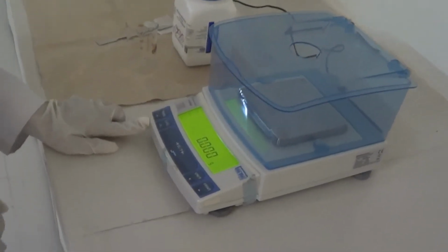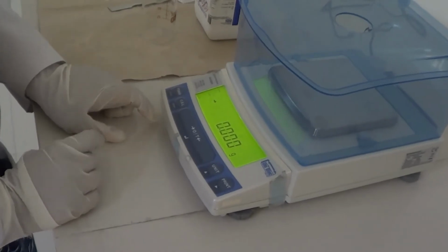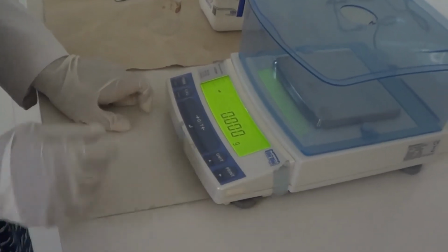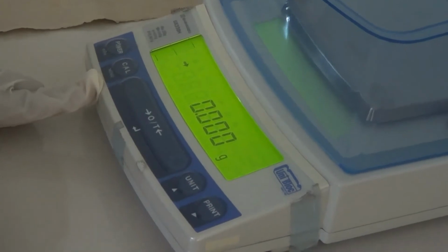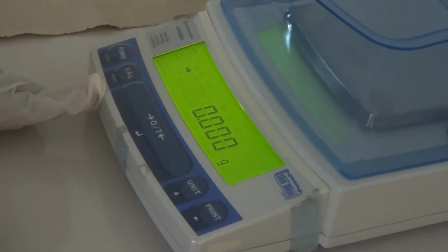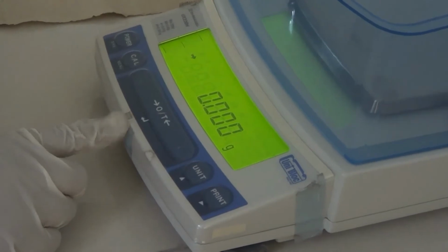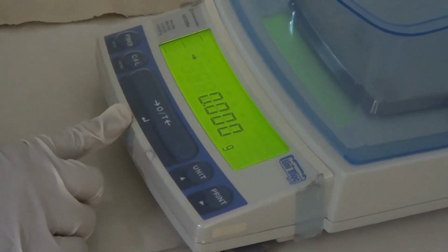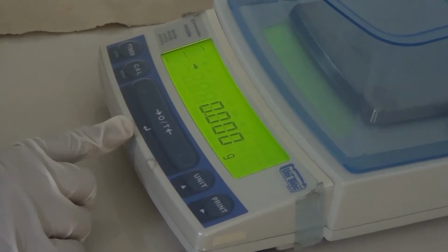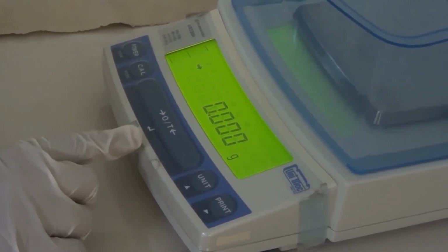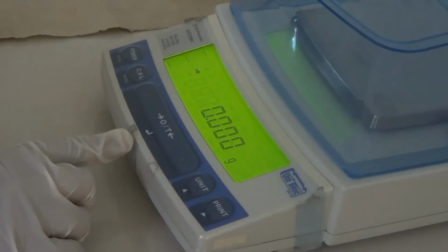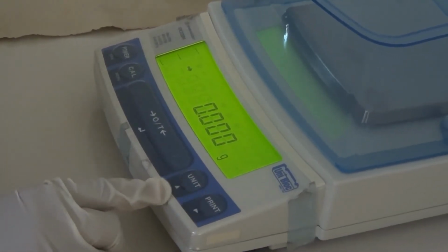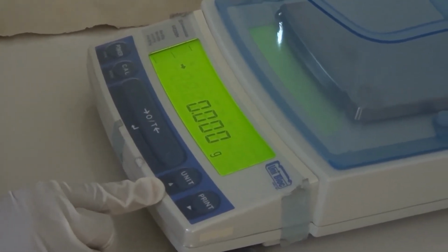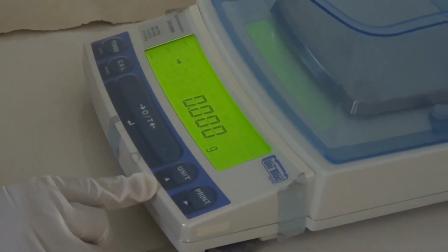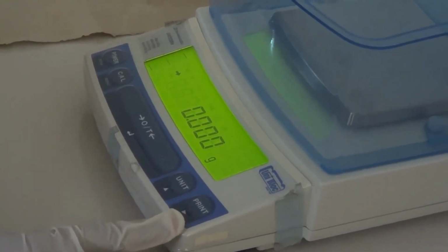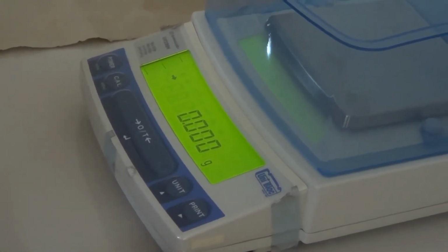Then we have a power button which is used for the standby and function. Then calibration button which is used for span calibration. This is tare button. This tare button is used to ignore the extra weight or the weight of butter paper or any container, and it only weighs the material. Then this is unit button. This converts the weighing unit into specific gravity unit. And then print. It is used when the weighing balance is connected with the printer.